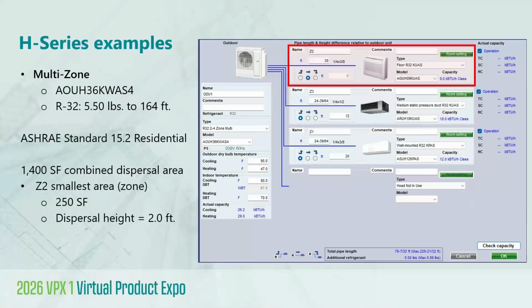It allows you to configure really any combination, or should I say allowable combination, of indoor and outdoor equipment, the number of zones, piping lengths, and options. So Design Simulator also will automatically adjust the delivered system capacities based upon your design conditions and piping distances. So for example, if you're designing something to other than 95 outside or 80 degrees indoors, or 47 outdoor. So Design Sim will ensure that all of your selected equipment is fully compatible and provides ever important total system charge info. So really, in summary, it serves as an effective safeguard for every AIRSTAGE project, not just VRF, but includes H-Series single zone and multi-zone systems.